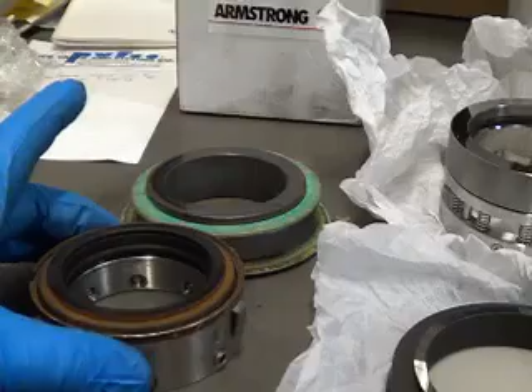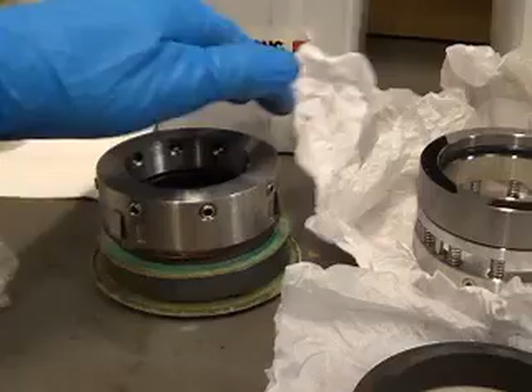I brought this over to show you an example of a similar type of mechanical seal that we use at Chill Plant 2. The difference here on this seal assembly is on the water side. On the newer pump, it's a vertical shaft, and the seal is in this position with the other part pressed in. Then you have little tabs that go into slots so you can load the spring, put it in place, tighten it down, then pull the clips out, and you get the proper tension on the sealing surfaces.